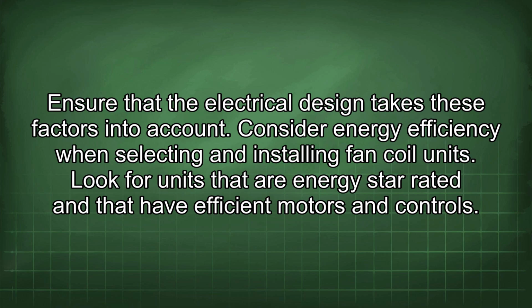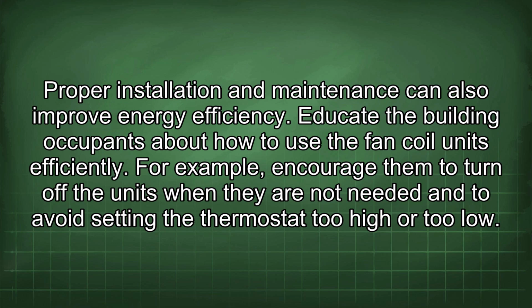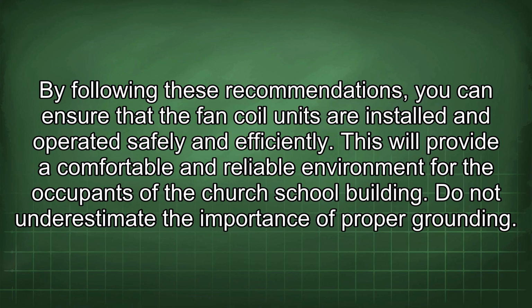Consider energy efficiency when selecting and installing fan coil units. Look for units that are Energy Star rated and that have efficient motors and controls. Proper installation and maintenance can also improve energy efficiency. Educate the building occupants about how to use the fan coil units efficiently. For example, encourage them to turn off the units when they are not needed and to avoid setting the thermostat too high or too low. By following these recommendations, you can ensure that the fan coil units are installed and operated safely and efficiently. This will provide a comfortable and reliable environment for the occupants of the church school building.